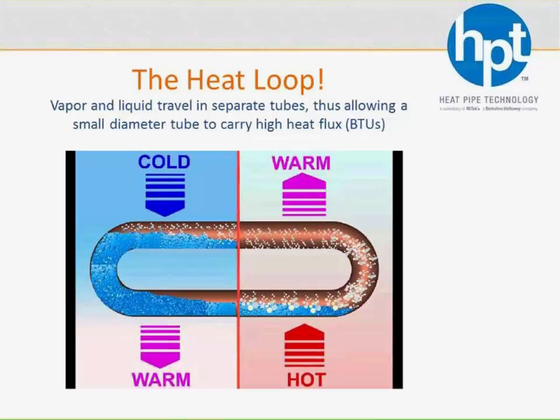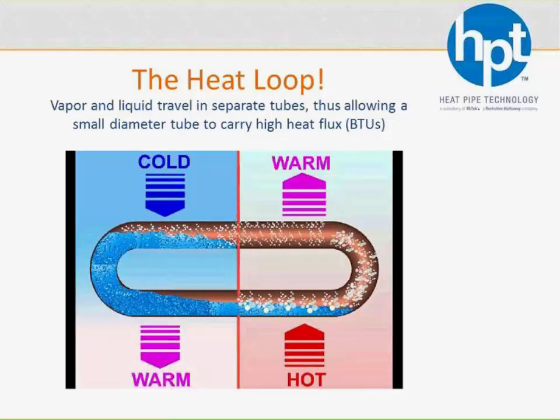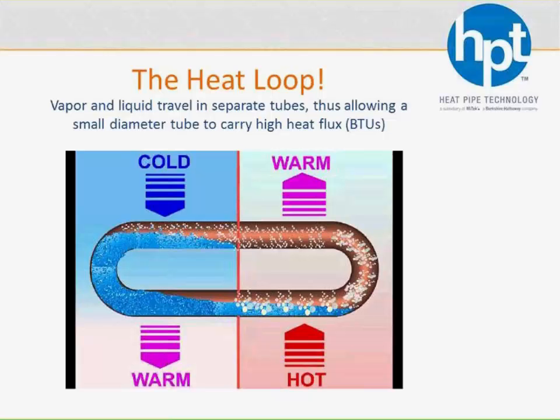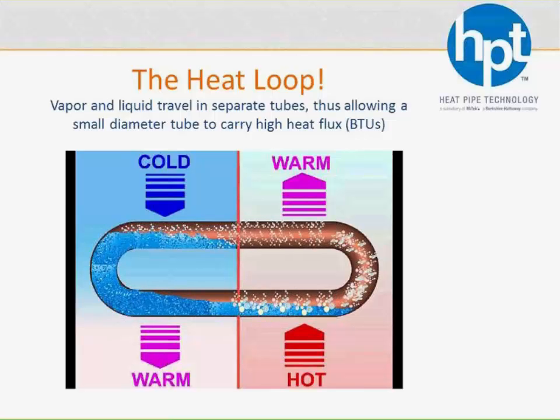So we at HPT have actually taken this one step further and developed what we call the loop circuit. So instead of one single tube with all the liquid and vapor going back and forth within the same diameter, we actually have more of a loop type circuit where the vapor and liquid is somewhat chasing itself in kind of a racetrack mode. So if you're looking at this picture and let's say the airflow is going in and out of your computer screen, if you didn't have any air or it was the same temperature, you would just have some liquid refrigerant sitting at the bottom of that loop. All of a sudden you apply warmer air, in this case to the right side. That refrigerant on that side is going to pick up the heat, boil, go up that loop, travel to the other end, give off the heat, condense back to a liquid, and keep going, in this case, in a counterclockwise type loop.